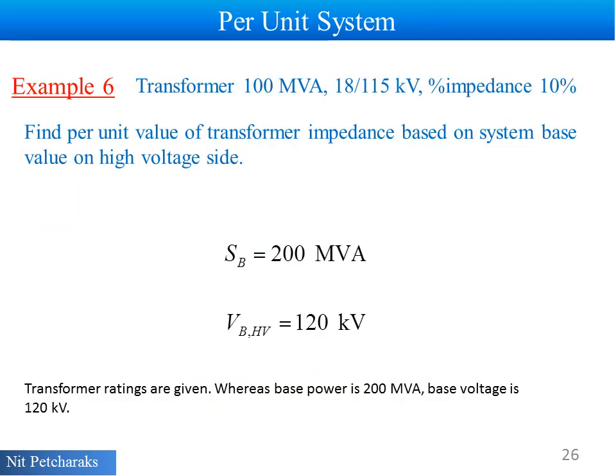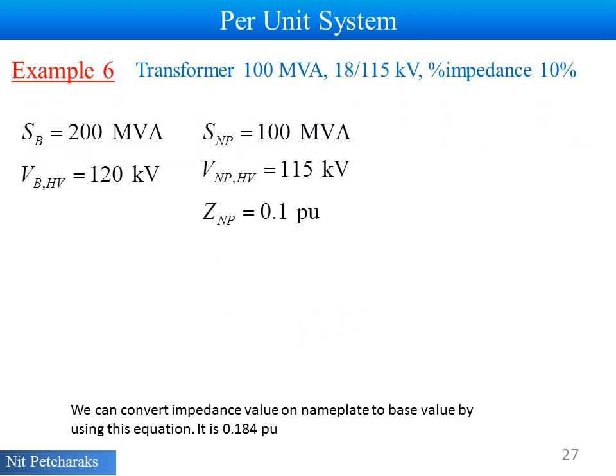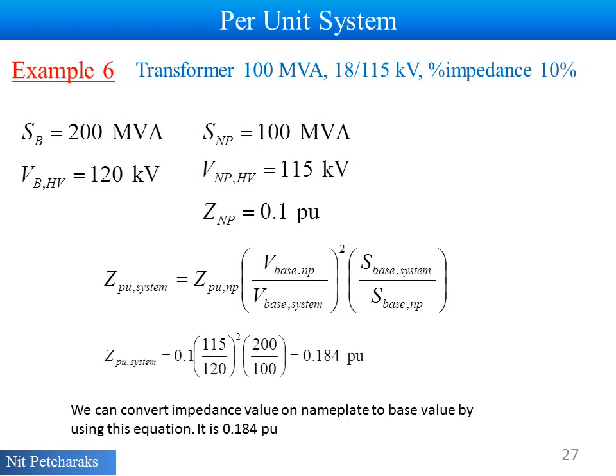Example 6: Transformer ratings are given. Whereas base power is 200 MVA and base voltage is 120 kV. Find per unit value of transformer impedance based on system base value. We can convert impedance value on nameplate to base value by using this equation. It is 0.184 per unit.